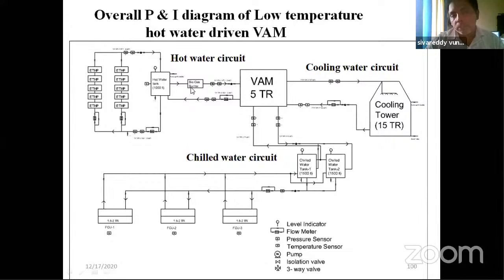I will show the plant also. It is connected to the VAM, and the VAM condenser is connected to the cooling tower. You see, the VAM capacity is 5 tons. Our theoretical COP we got is 0.7, but we are assuming the practical COP will be only 0.5.